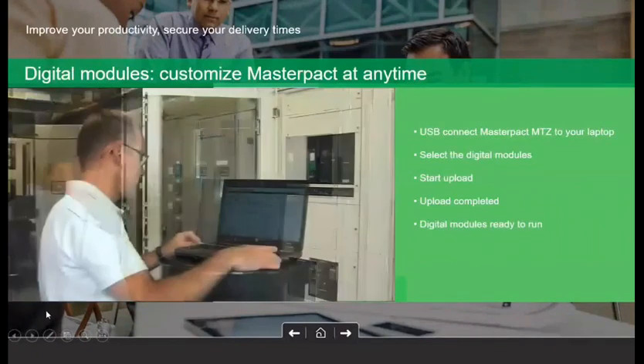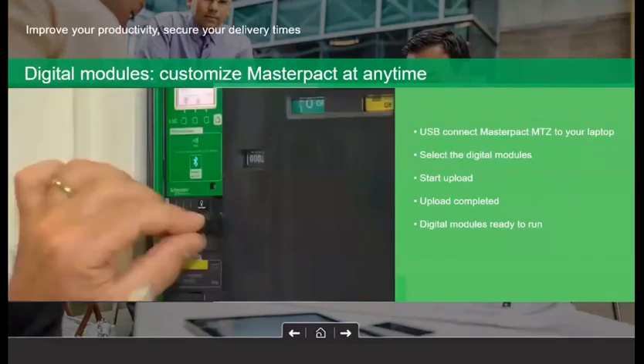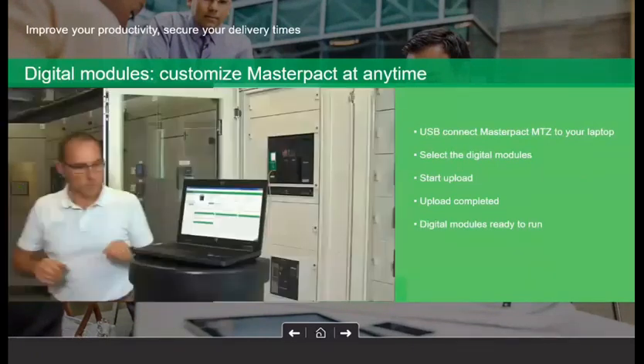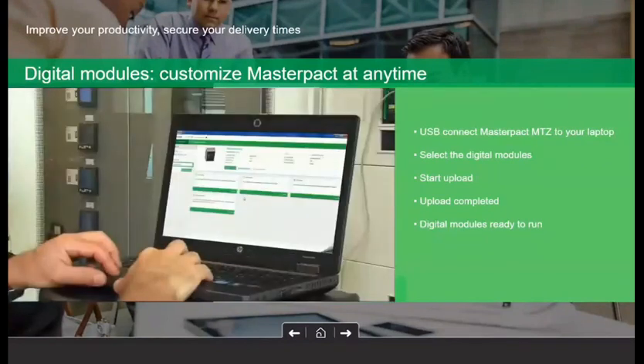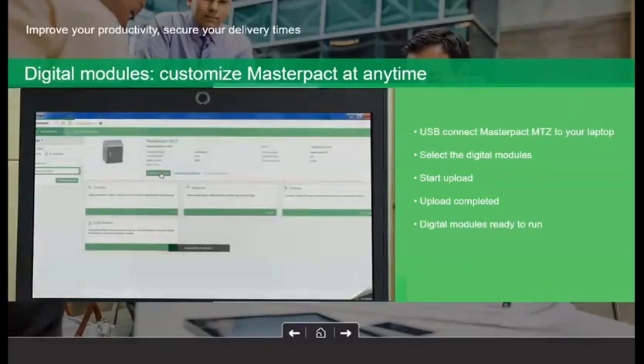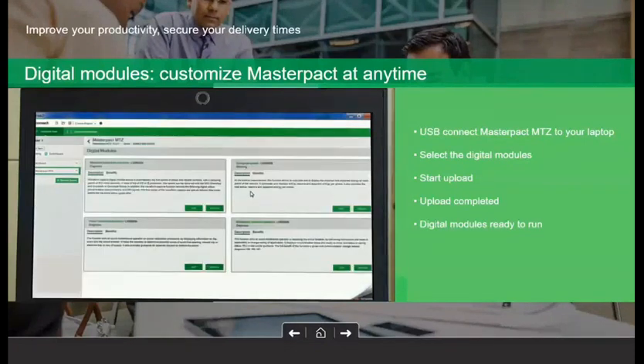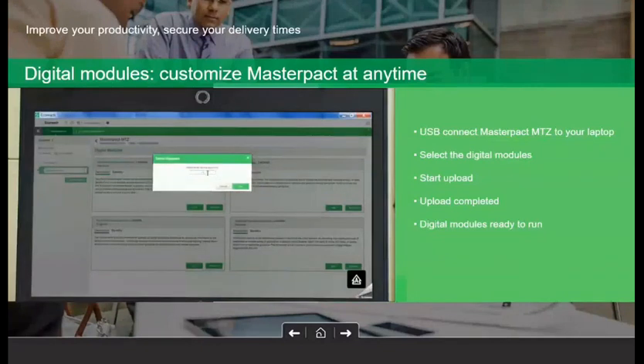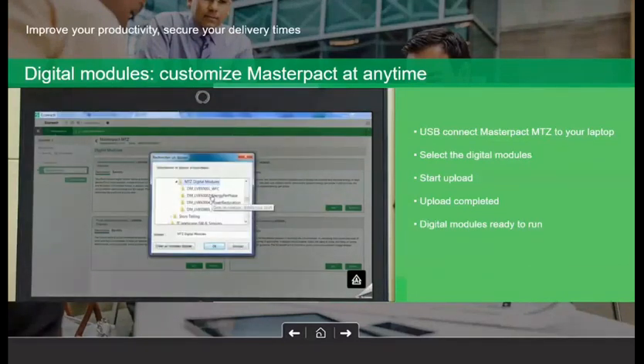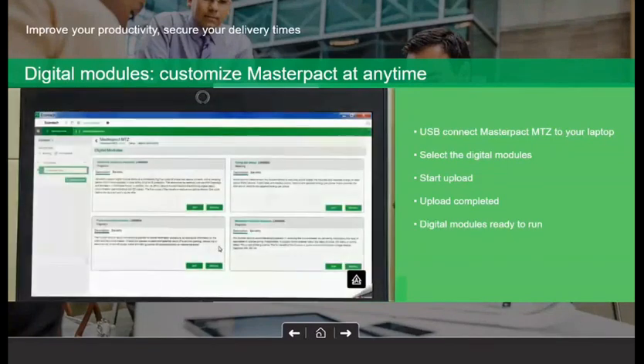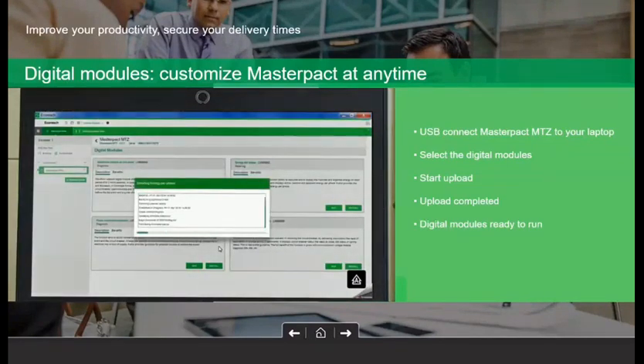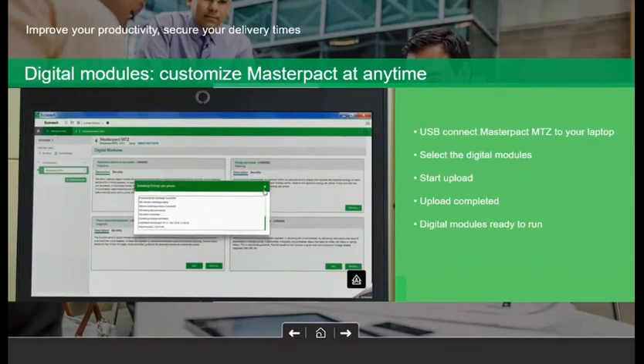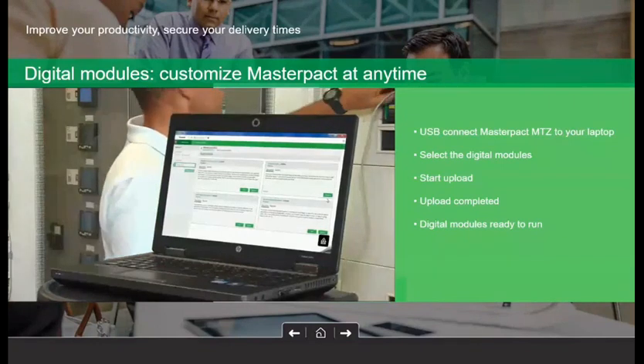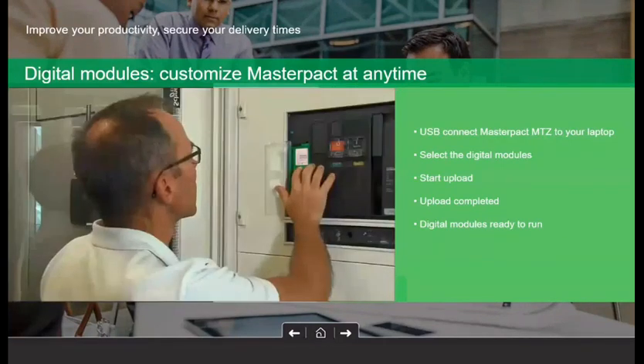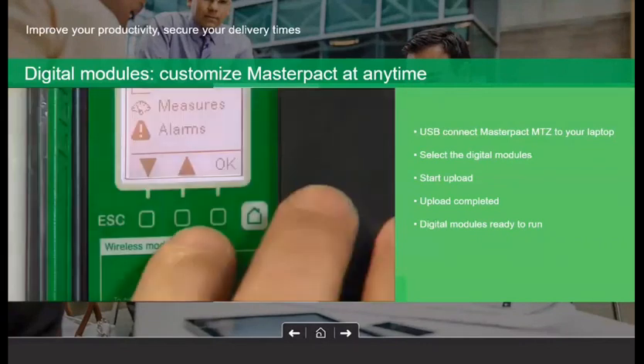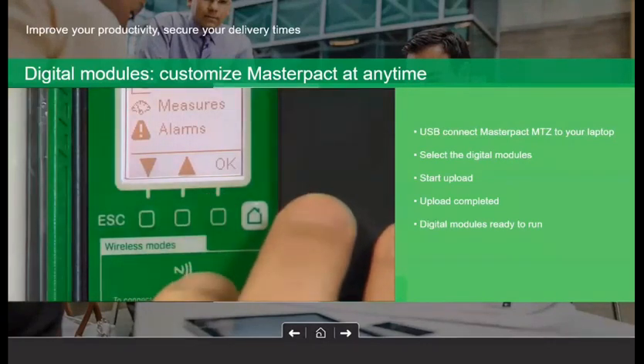In just a small video of a few seconds, you will come to know how easy it is to install the digital module. You just have to connect the USB cable to your ACB. Right now the ACB is under operation. You select the digital module, connect to the ACB, and select the digital module, or which feature or firmware, you want to upgrade in the breaker. It will ask you for a password. Once you enter the password, select the particular digital module. Once the digital module is selected, you can just click download. In just 5 or 6 seconds it will download the entire digital module. Okay, the task is done, your breaker is ready for the use of that particular feature. It will just take a few seconds to upgrade the feature of your breaker.